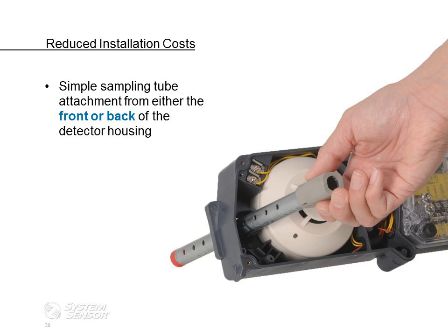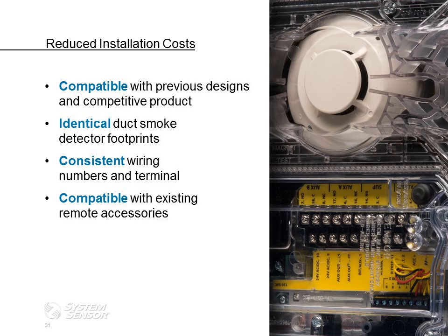Reduced installation costs, savings. It's a simple sampling tube attachment. Our sampling tube is just a snap and click, and it can be mounted from either the front or the rear of the housing. There are no tools required. As well as on the sampling tube, it is keyed so that you have an arrow that shows you which way the hole stays, so you can make sure that it's put into the airstream.